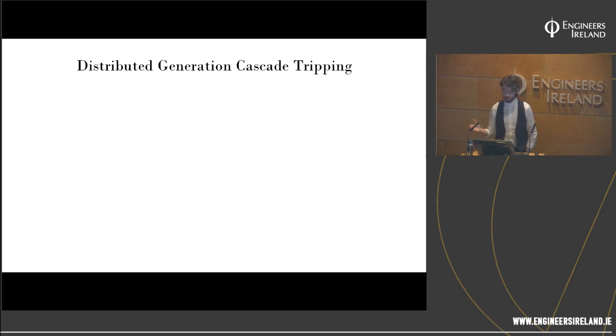So sometimes there can be an event on the system, and these protection systems on the distributed generation can maltrip. Now, if you make them less sensitive, then they mightn't actually detect the thing they're trying to guard against in the first place. So there's a balance there. I'm not sure if you've heard before, but in Germany and throughout Europe, I think it was called the 50.2 hertz phenomenon. So all the PV that was installed, their settings said, okay, if you go to 50.2 hertz, trip me off.